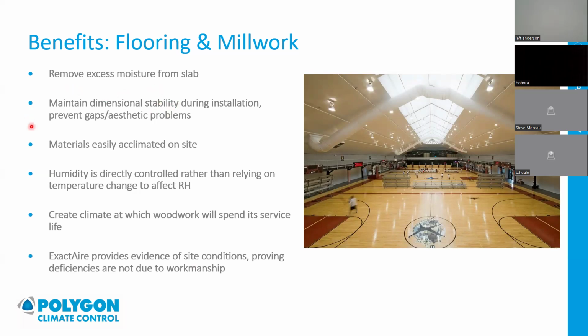With materials, you can maintain stability by acclimating them on site—you can stick a pin meter in them and check on them, or put a sensor in there to provide continuous data on the moisture content of that wood flooring, as well as a record of the air, showing we've maintained conditions throughout construction, know where it was stored and for how long, know it's ready to go, and are maintaining the space while it's being installed. So there are a lot of benefits to directly controlling humidity as opposed to just heating and hoping humidity lands where you need it. Really, we're trying to create the climate in which that woodwork will spend its service life—the permanent rooftop equipment that'll be in place has been engineered and spec'd to hold conditions within a certain range in that building, and we're basically trying to recreate that range using equipment on site to control conditions.